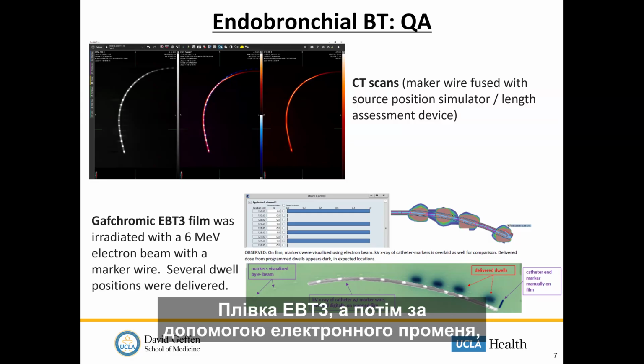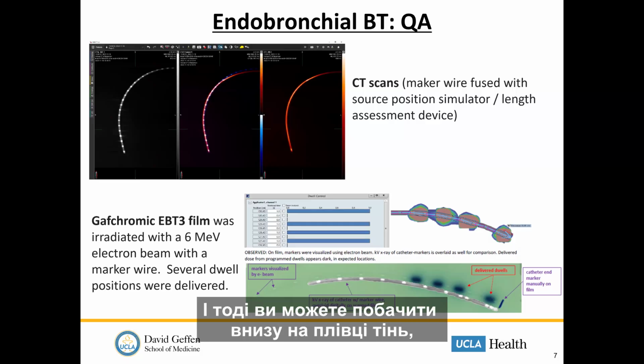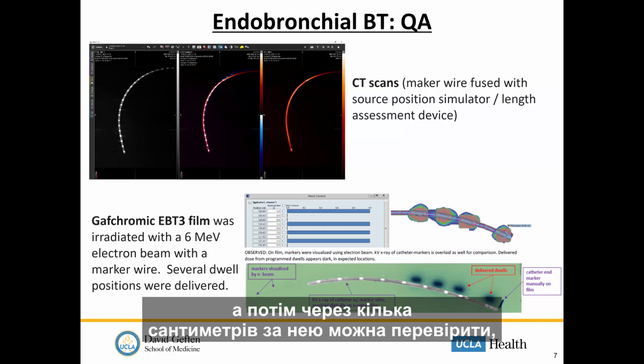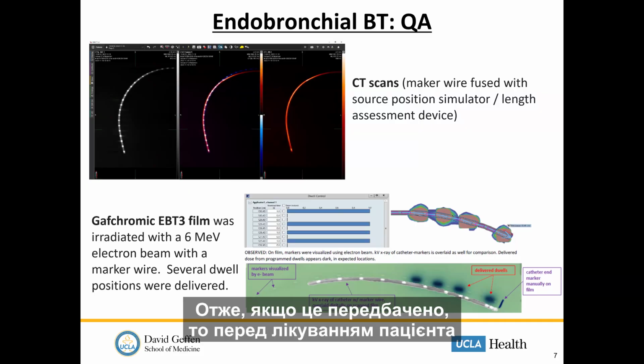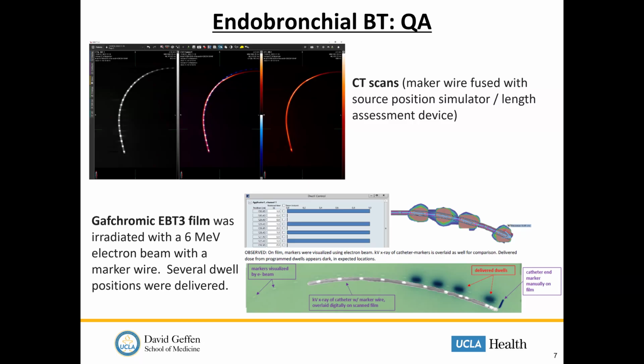And also, we can tape this on the Gafchromic EBT3 film, and then using an electron beam, like 6 MeV to 20 MeV, irradiate about 300 to 400 MUs on the film. And then on the bottom of the film, you can see the dummy marker shadow. Then you can program delivered dwell positions at the tip, and a couple of centimeters behind that, and verify that the radiation source can be delivered at the first dwell position at the tip. So physicists must do this QA before treating the patient.